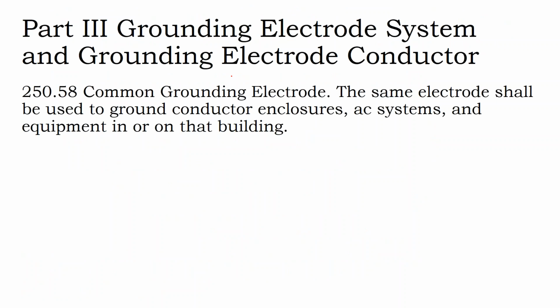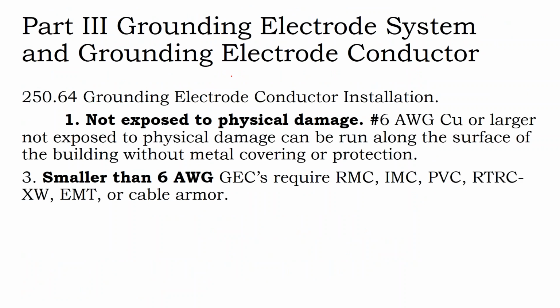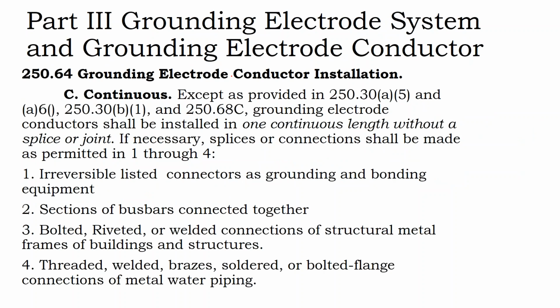Your grounding electrode should be common across a single building, but we saw that there is an exception for separately derived systems. Not exposed to physical damage, and if your grounding electrode conductor. So remember, your grounding electrode conductor is what connects your building grounding system to the ground rod. It's the last leg of the journey to your ground rod. If it's smaller than number 6, you have to protect it in conduit. If it's larger than number 6, you don't. So you might look at a building and say, well, why is that ground wire exposed? Why is it just hanging out on the side of the building? Well, it's because it's number 6 copper or larger. Now, whether or not that looks better or worse than protecting it is a separate issue.